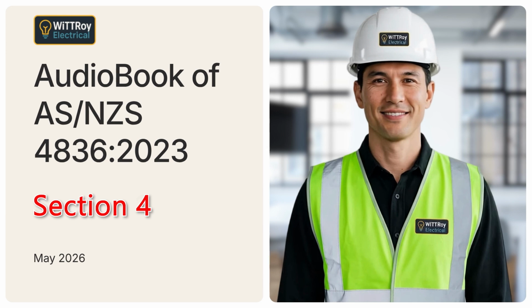Clause 4.3.13. Cutting cables or wiring enclosures. Clause 4.3.13 explains cutting cables or wiring enclosures. Cutting must not proceed until the correct processes have been followed and tests have proved that the cable is isolated before cutting. If isolation of the conductors inside a cable or wiring enclosure cannot be conclusively proven, the cable or enclosure must be treated as if it contains live conductors.